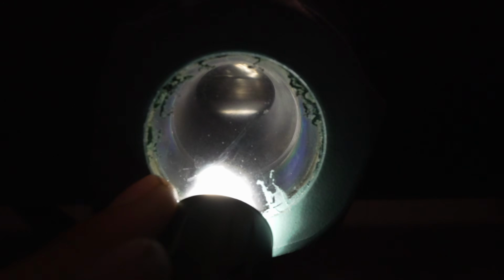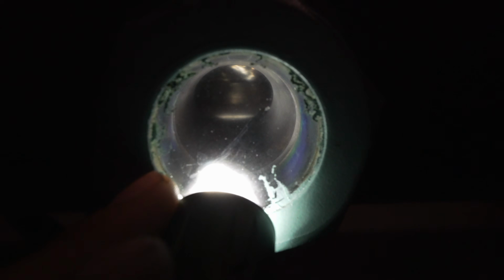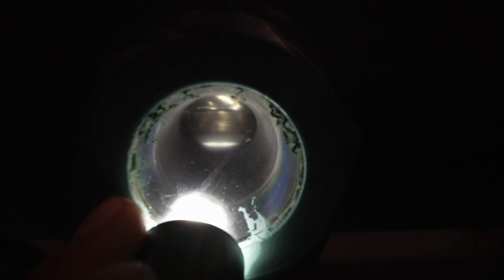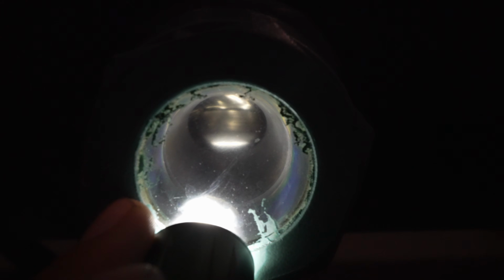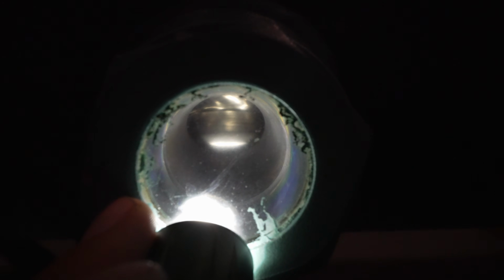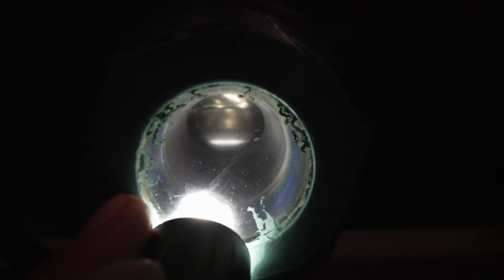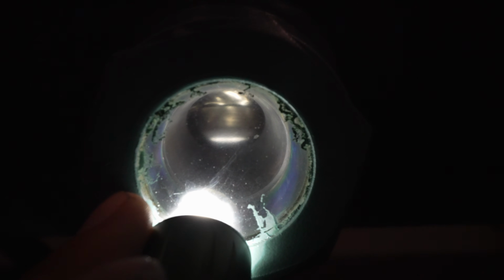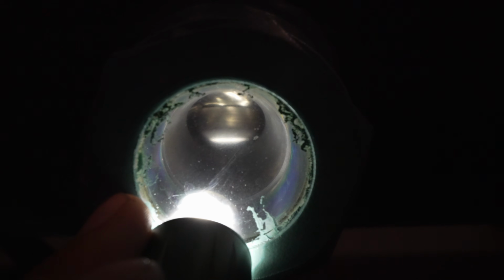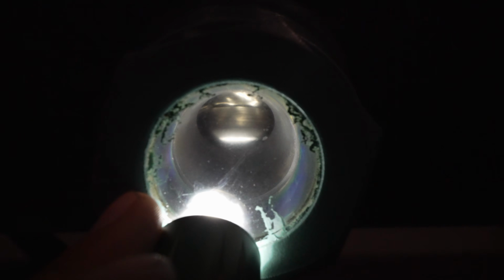What they tell you at the factory is you want to be looking through this sight glass dead on, and your refrigerant level should be 3/4 of an inch at minimum above that plate as solid liquid. Typically, we aim for 3/4 to 1 inch above that, so that we can make sure that we're maintaining a high enough level that turbulence is not allowed to impact the tubes in the subcooler.